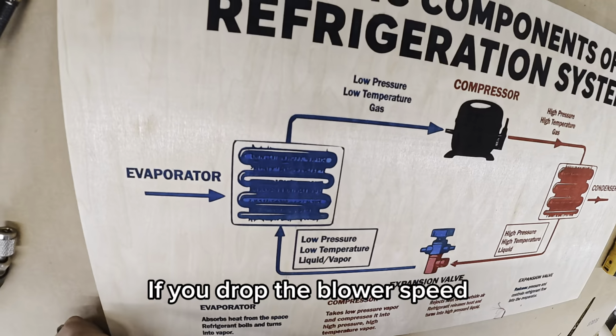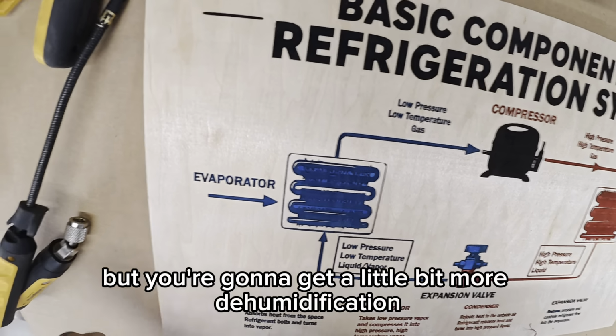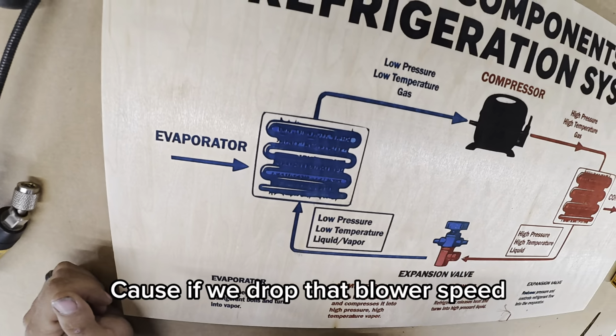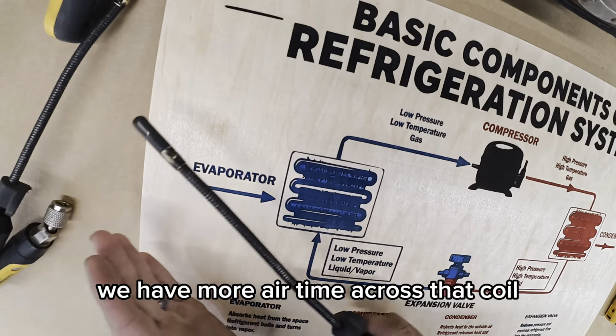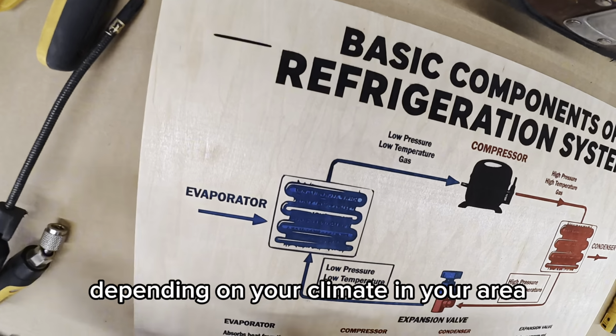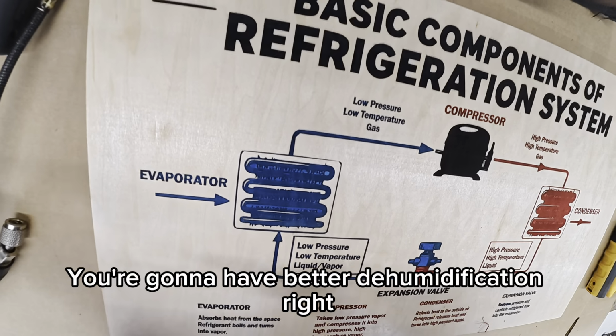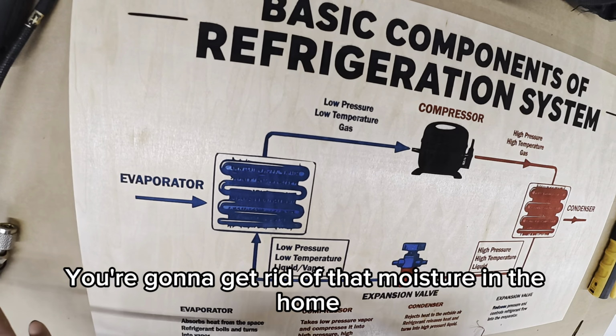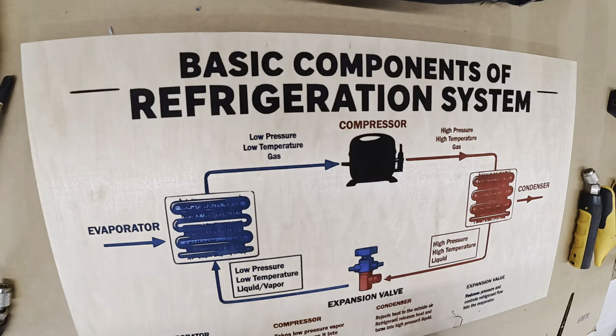If you drop the blower speed, it's going to drop the pressure a little bit, but you're going to get a little bit more dehumidification, right? Because if we drop that blower speed, we have more air time across that coil. Depending on your climate and your area, you're going to have better dehumidification. You're going to get rid of that moisture in the home. I live in the Southwest.